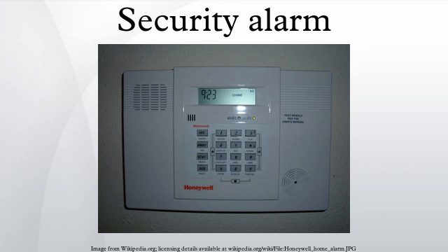Smoke, heat, and carbon monoxide detectors. Most systems may also be equipped with smoke, heat, and/or carbon monoxide detectors. These are also known as 24-hour zones. Smoke detectors and heat detectors protect from the risk of fire, and carbon monoxide detectors protect from the risk of carbon monoxide. Although an intruder alarm panel may also have these detectors connected, it may not meet all the local fire code requirements of a fire alarm system.